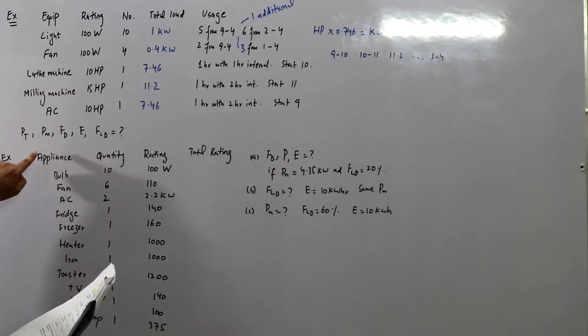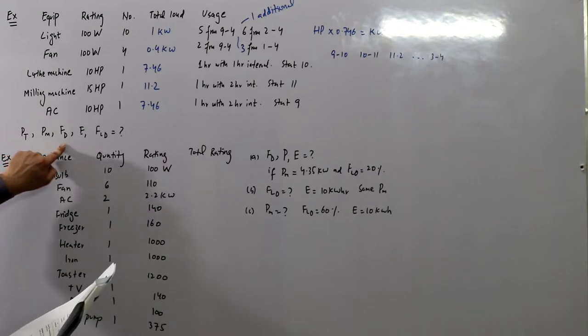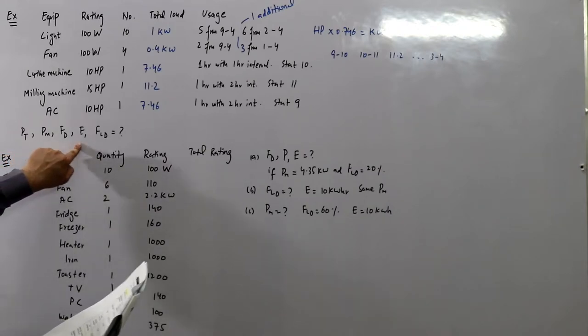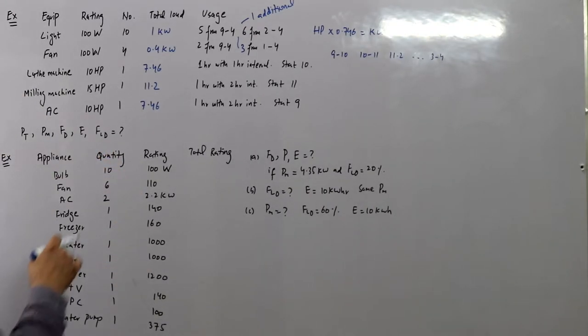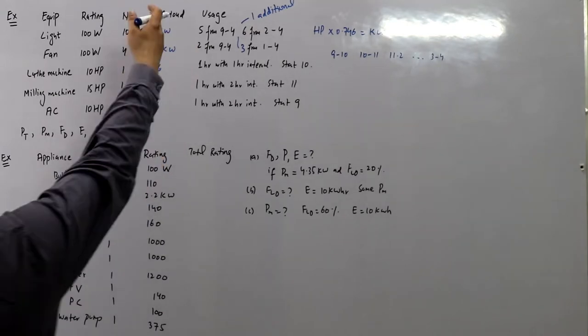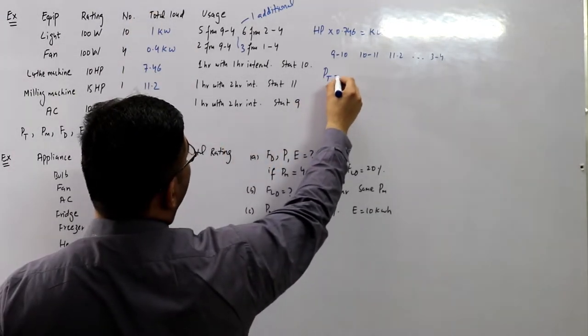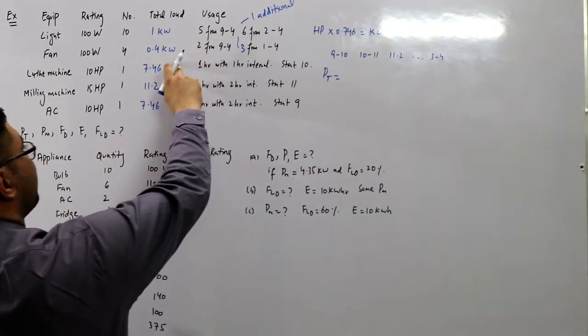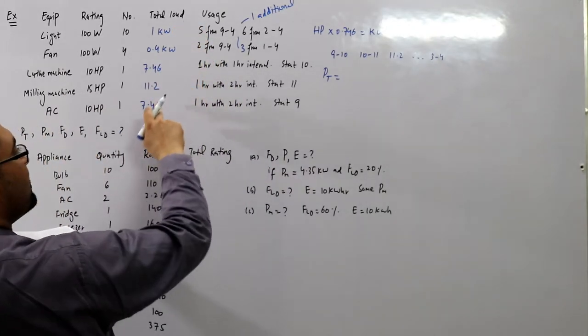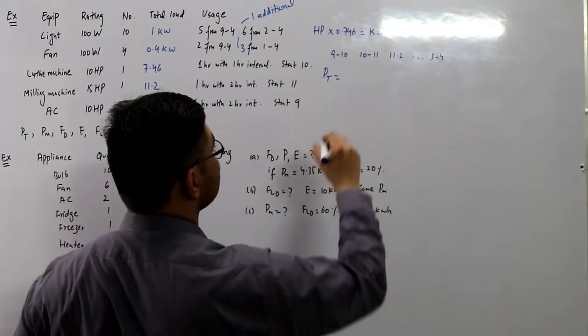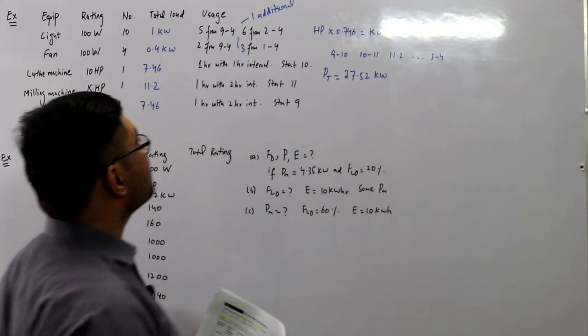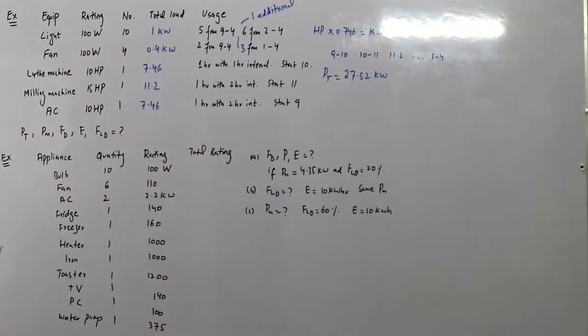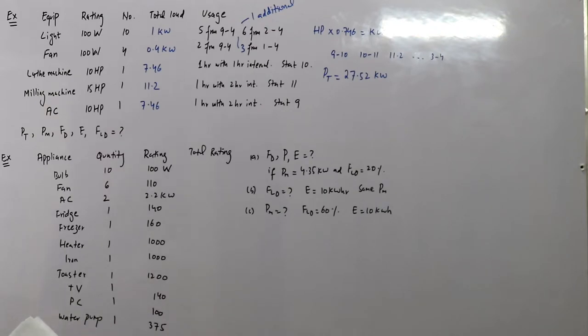The question asks to find: the connected load, the maximum demand, the demand factor, daily energy consumption, and the load factor. The connected load pt = 1 + 0.4 + 7.46 + 11.2 + 7.46, which comes out to be 27.52 kilowatts total connected load to the system.